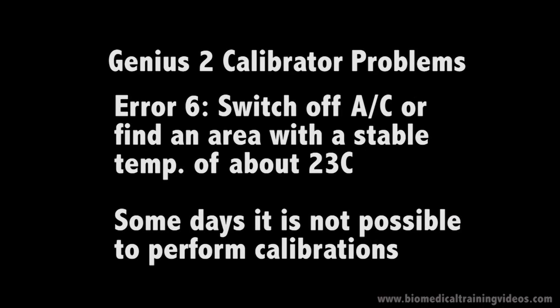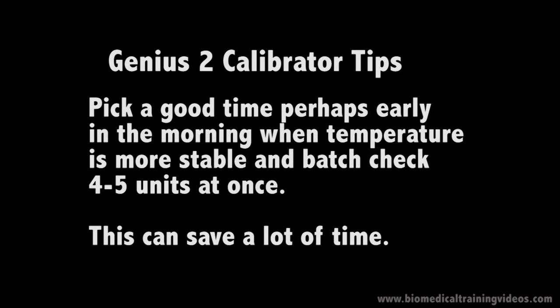Okay, just having a look at some of the problems that may come up during calibration. Again, I've mentioned error 6, which relates to the ambient temperature, so try and find a room that's fairly stable in temperature. Somewhere around 23 degrees usually works. And some days you may just find it's not possible to get a stable temperature. So pick a good time, perhaps early in the morning or later in the afternoon when the temperature's fairly stable.